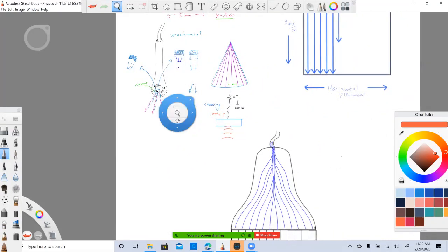So let's see. Mechanical, single, circular, disc-shaped, active element. It is mechanically steered. It is fixed focus, either by an internal or an external focus. You damage one crystal, you're done. And that's it. I think those are the major things to think about with that.